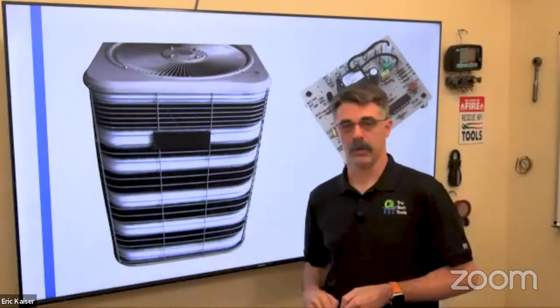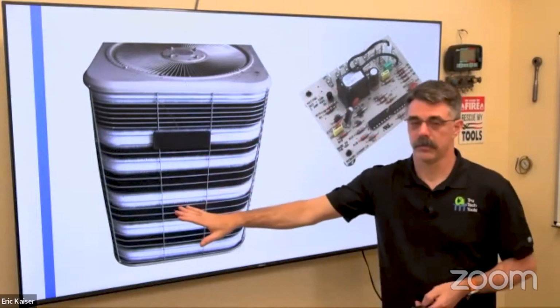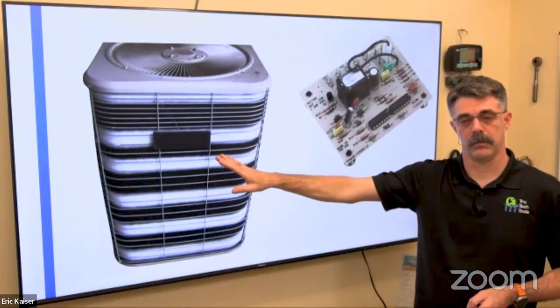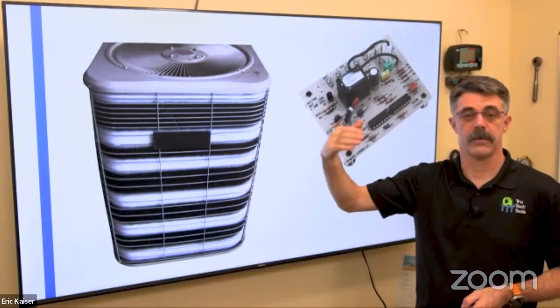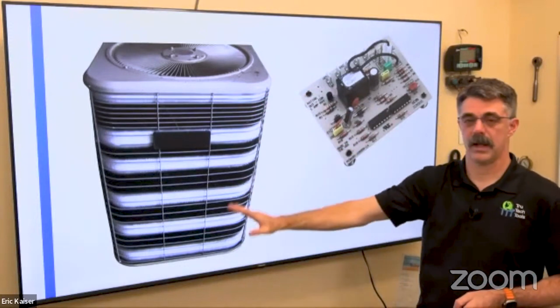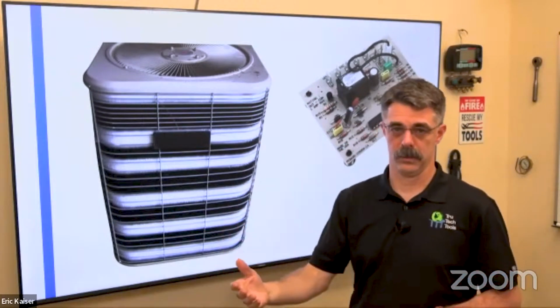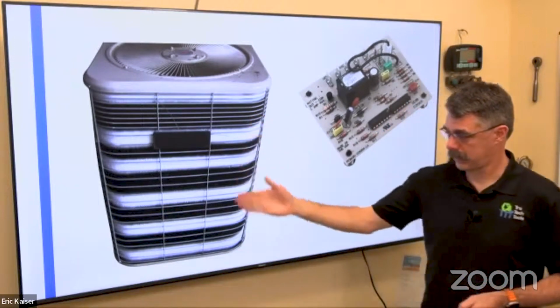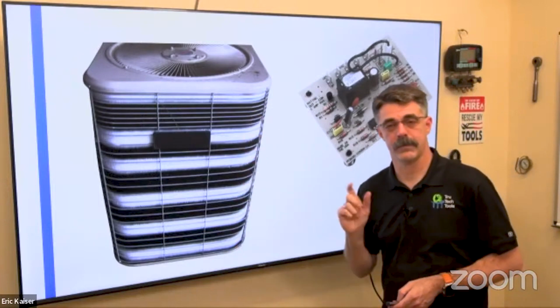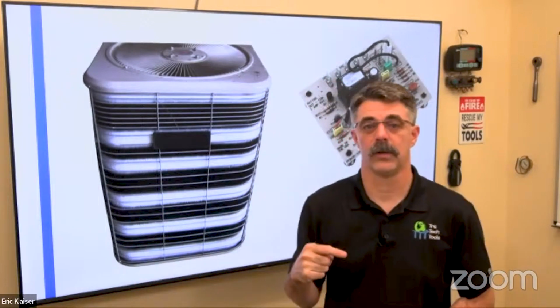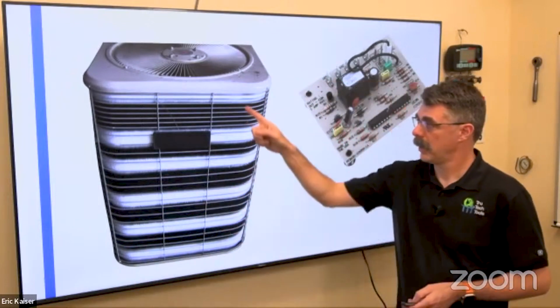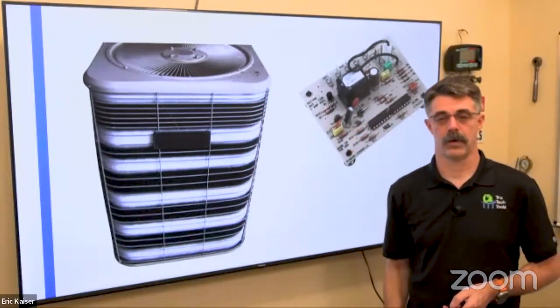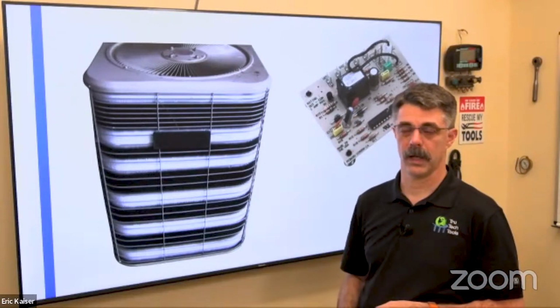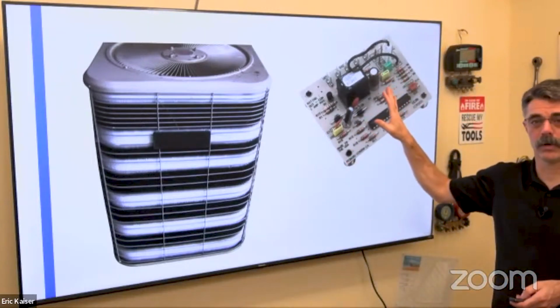One of the first things I recommend people look for when selecting a heat pump is at the defrost. So when a heat pump is running, the outdoor coil is often below 32 degrees or freezing temperature, even when the air temperature is higher, because we have to make that outdoor coil colder in order to absorb heat into it. So moisture on the air will frost on that coil, and at a certain point, we have to reverse that heat pump back into a cooling unit so it's not heating the house. It's going to take a few minutes, pull just a little bit of heat out of that house, put that heat into the outdoor coil, and melt all that frost off of there, and that frost is going to run away. Okay? That's all controlled by something called a defrost board, right?